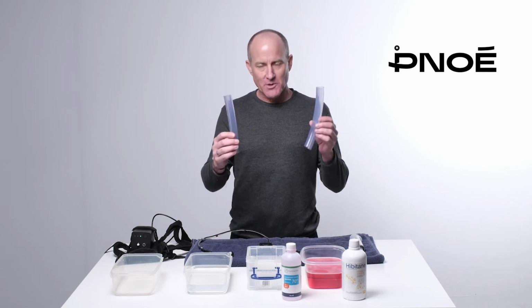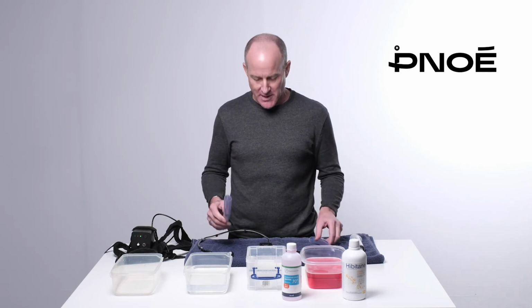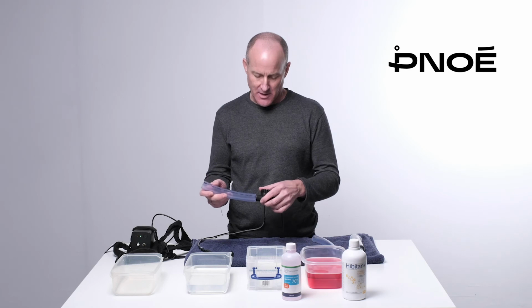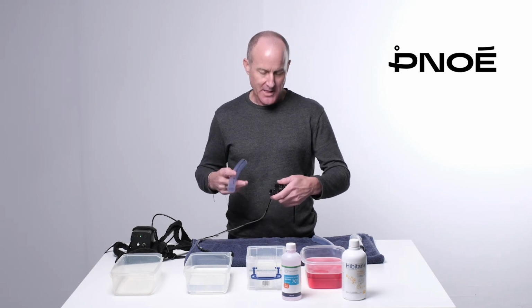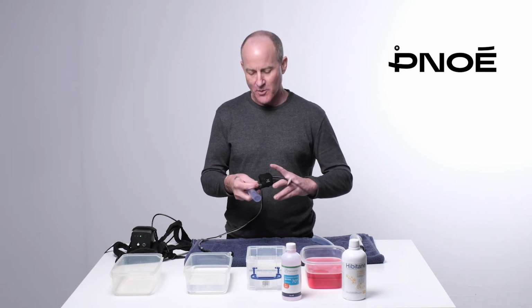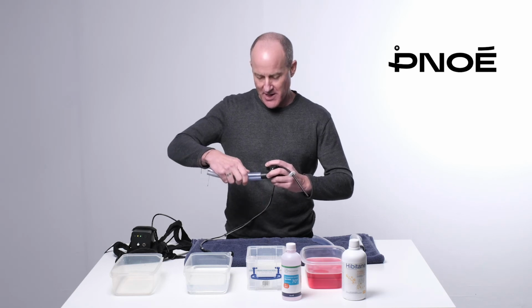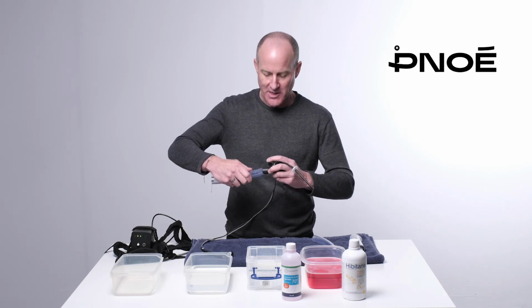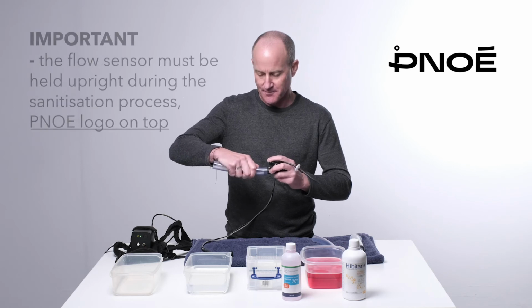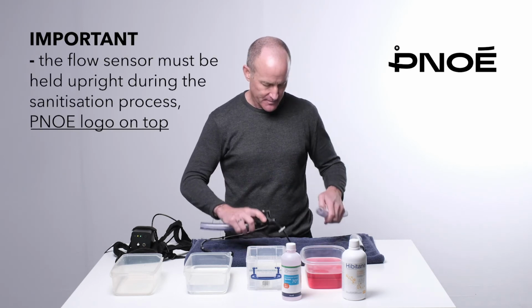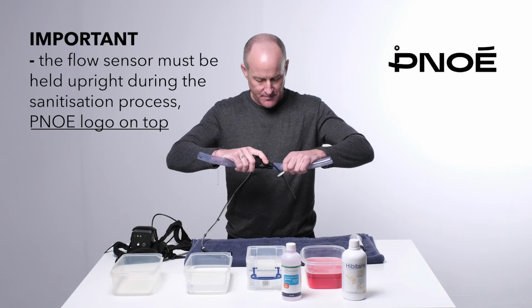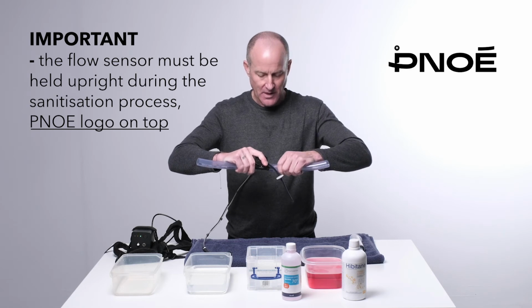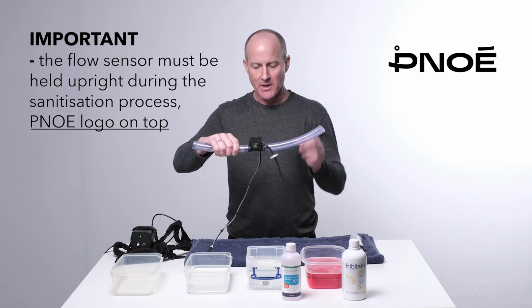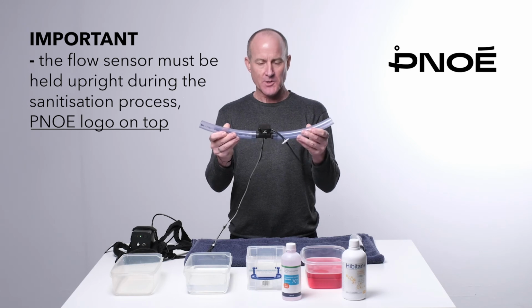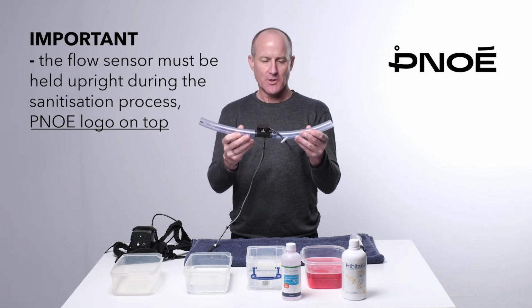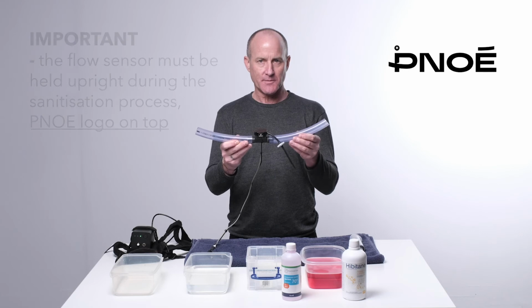To start the cleaning process, you need to attach the rubber tubes to either end of the flow sensor. Again, be very careful when you're putting on the plastic devices that you do not put any pressure on the cabling. They don't have to be pushed all the way on, but you want to make sure that they're well secured, and you want to make sure that the curves are going upwards.